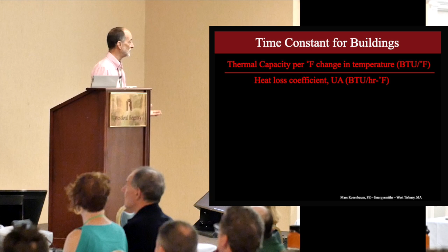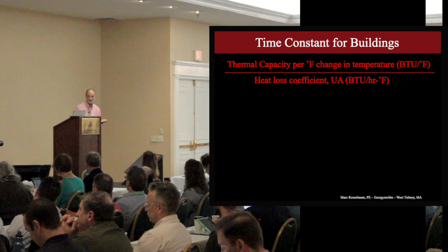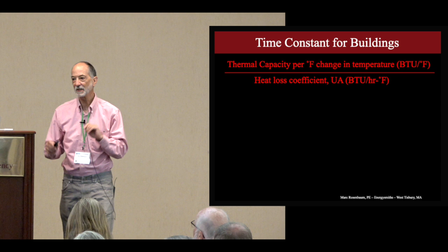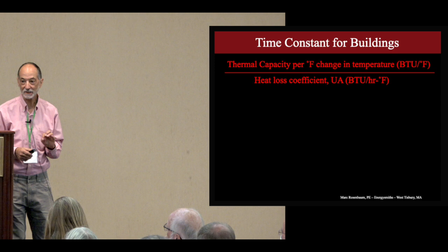Anyway, how many BTUs does your building need to raise it 1 degree Fahrenheit? Or drop 1 degree Fahrenheit? That's the thermal capacity. So a building that's more massive takes more BTUs to change its temperature. Does that make sense? Stop me when I really stop making sense. I don't mean like the big suit of David Byrne. Okay, divide that by the heat loss coefficient, BTUs per hour per degree Fahrenheit. And if you actually do unit cancellation, which is something if you're old you learned to do, so you didn't get the wrong answer, you get hours. You get time constant in hours.